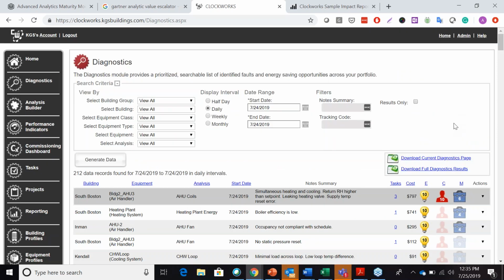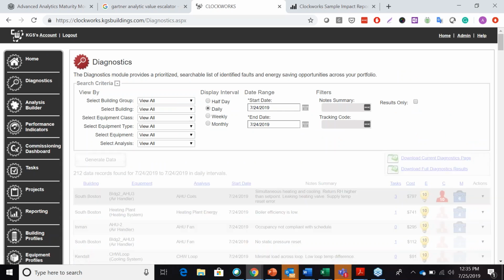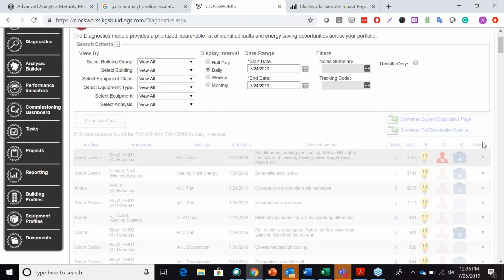I'll zoom back out a second, look at the overall list here. So far, we've been talking about energy. I'm going to jump to the other priorities here. For a number of the teams that we work with, energy is actually not the top priority. So if I click on comfort here, I'm going to get a very different type of list. And again, this is what's affecting our ability to meet space temperature and humidity set points in our zones. So pulling up the range of VAVs or fan power boxes that may be having issues there with supply air temperatures being too high or too low, with supply flows being off, that kind of thing.